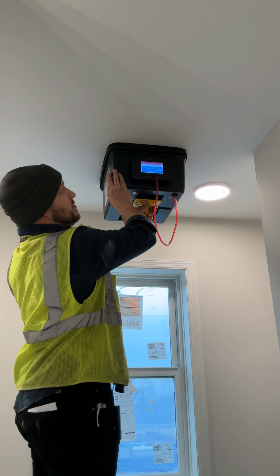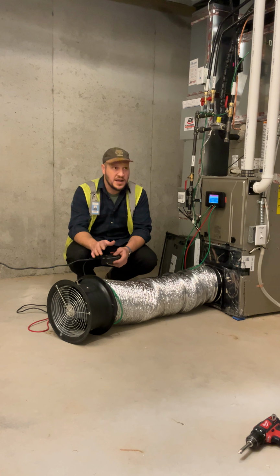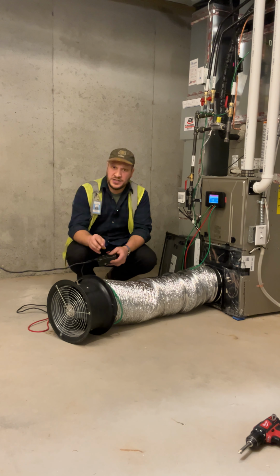During our final inspection, we're going to measure duct leakage as well. So here we've got our duct blasters set up. We're going to measure total duct leakage, which is the entire system. We'll measure the CFM of leakage there, and we'll also measure leakage to the outside. That's going to tell us how much outside air is getting into our duct system.